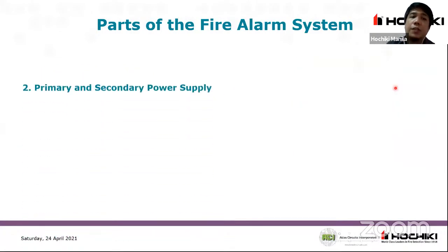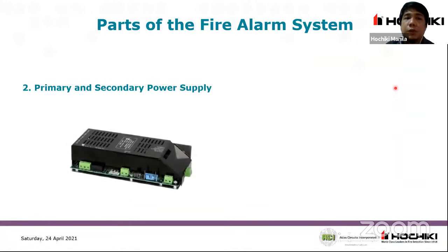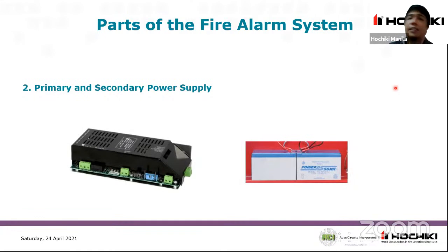Next, we must have the primary and secondary power supply. Of course, we cannot have this fire alarm control panel without a primary source of power - this is our AC, usually 220 to 230 volts AC. Next is the secondary power supply. Based on the NFPA code, we need a secondary power supply that will switch in automatically in case the primary source fails.